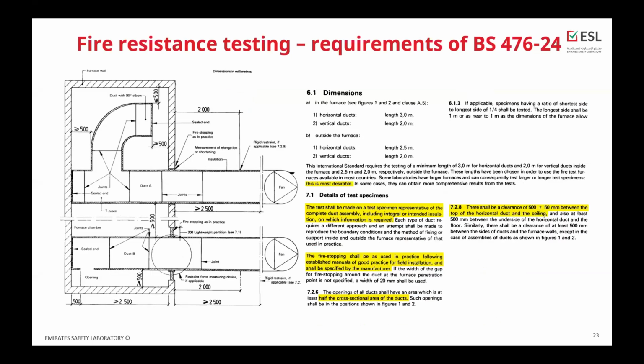So what are the requirements for you to create the duct for the testing? You have the limits, you have the minimum numbers for the length and the size of the duct for horizontal, which is a minimum 3 meters long inside the furnace and at least 2.5 meters long outside the furnace. The cross section is referred to as a ratio of 1 to 4, 4 to 1 width to height. So mostly we are testing 1 meter width of the duct and 250 millimeters of height. Duct A has a branch, as I said. The branch has the same cross section as the main duct.